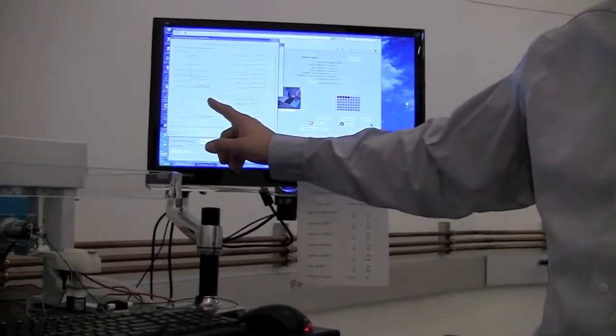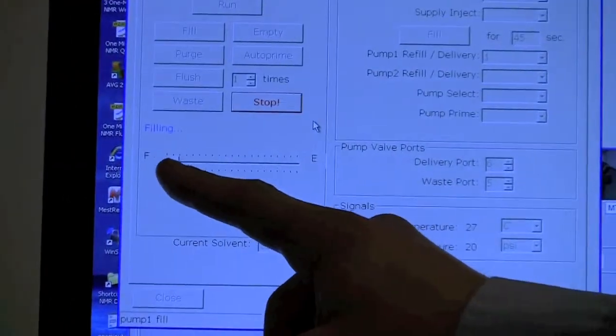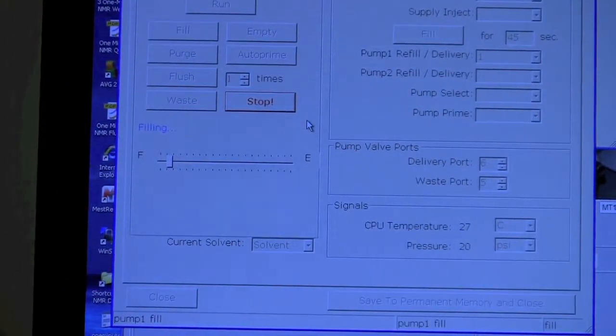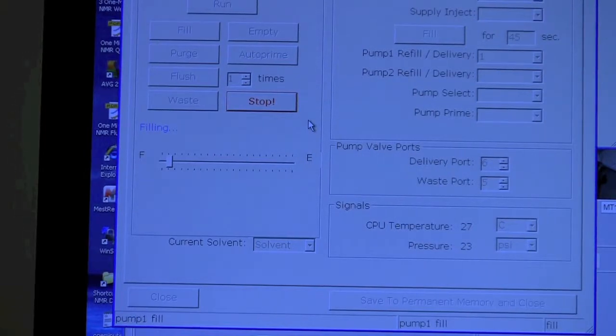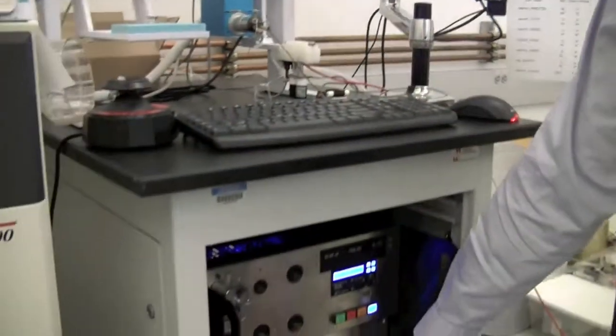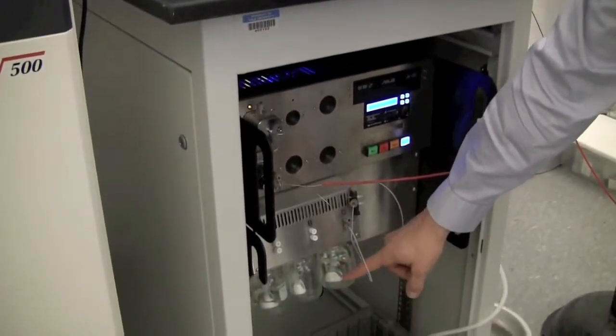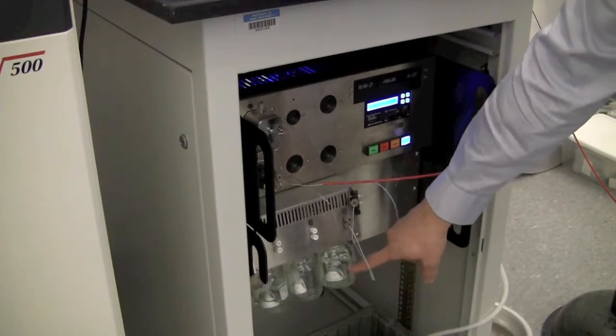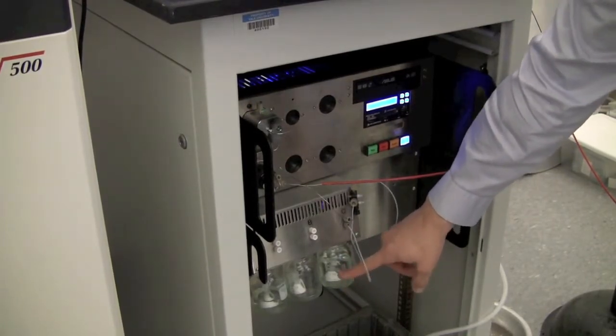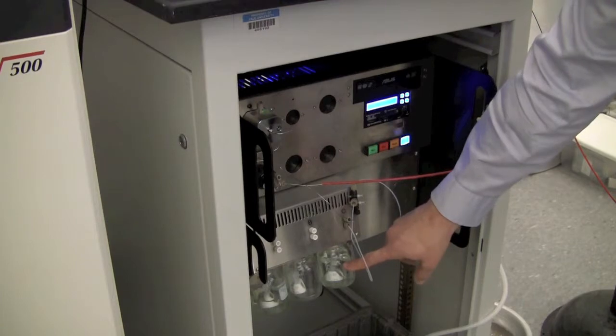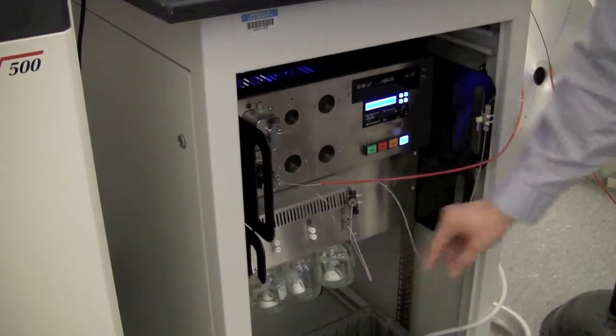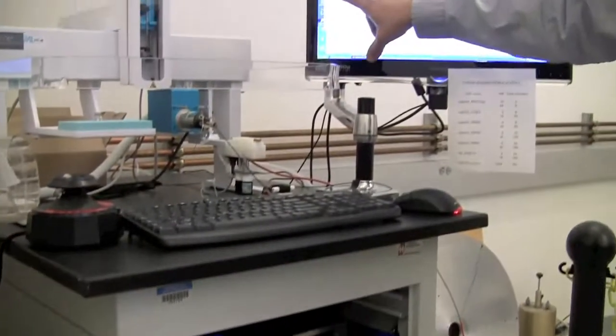Okay, now that we've waited, the indicator went all the way to empty and then refilled, and it's almost to the end of filling. So we will wait for it to finish filling here. That means that the syringe has refilled with solvent from the reservoir down here. One thing you can check to make sure is that there actually is solvent in the reservoir. For chloroform, we're using reservoir C. If the solvent is very low or empty, please let me know. In this case, it's fine. So we come back up here, and now it says ready, so it's been refilled.